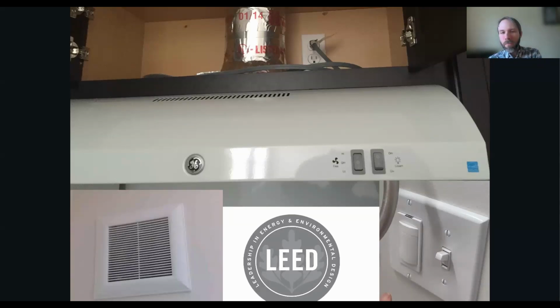And so the way we look at this is meeting ASHRAE 62.2-2010, which is a ventilation standard. This includes local kitchen exhaust at 100 CFM or higher, tested by the rater and vented outdoors. Bathroom exhaust at 50 CFM or higher, tested by the rater and vented outdoors. And total unit ventilation rates, either continuous or intermittent, of at least 20 to 50 CFM, again tested by the third-party rater. This can be accomplished through the bath fan or an inline supply fan through the furnace or heat pump, or ideally by an energy recovery ventilator, which scores more points than in LEED or NGBS.